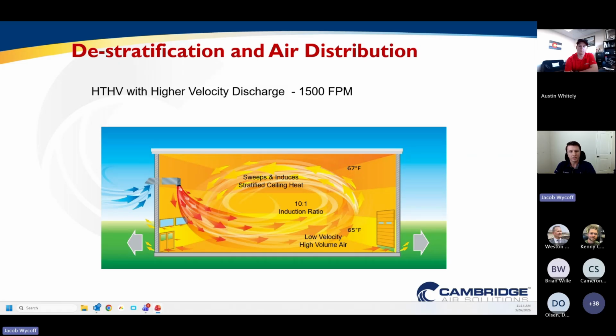Are you worried about stratification? Well, we avoid that with our very high velocity discharge coming out of the unit at a 45-degree angle, anywhere from 1,500 to 2,200 feet per minute, sweeping that air down across the floor and back and sweeping and inducing any stratified ceiling heat, getting extremely even temperatures throughout the facility. The high discharge temperature also gives us a very high induction ratio, a 10-to-1 induction ratio, meaning for every CFM of air that our supply fan provides, we're moving 10 CFM of air around in the space that was already there. Because we're positively pressurizing the space as well, we're reducing the infiltration around the exterior, which makes for much more comfortable perimeters of the space.